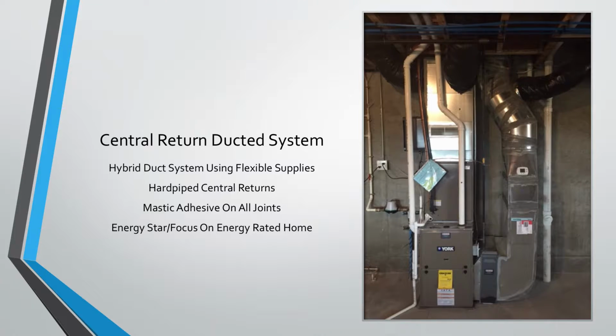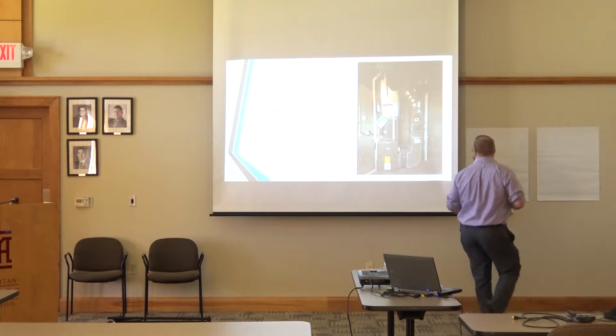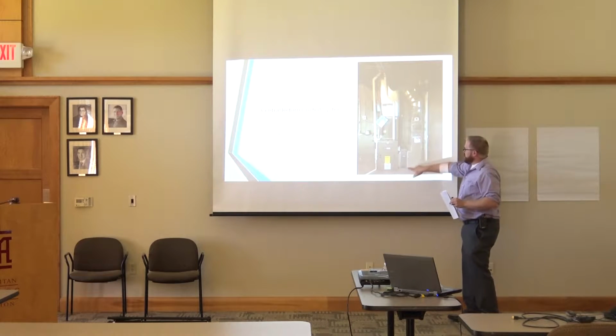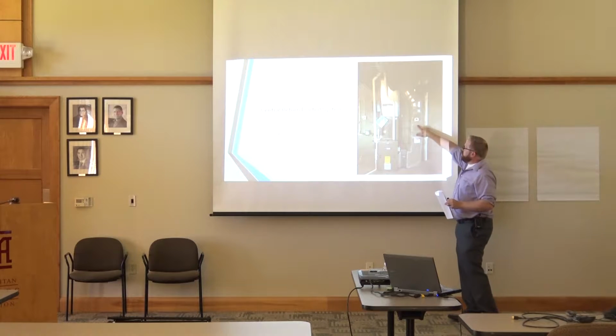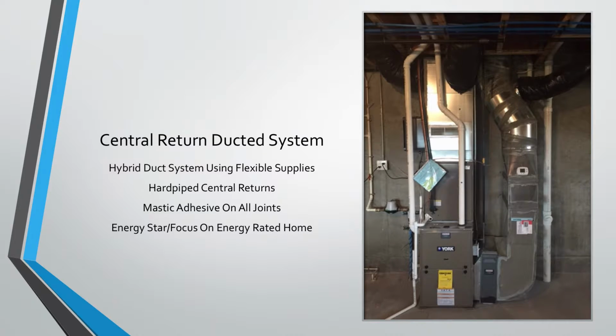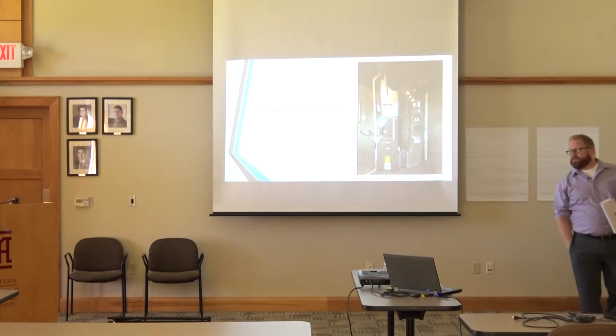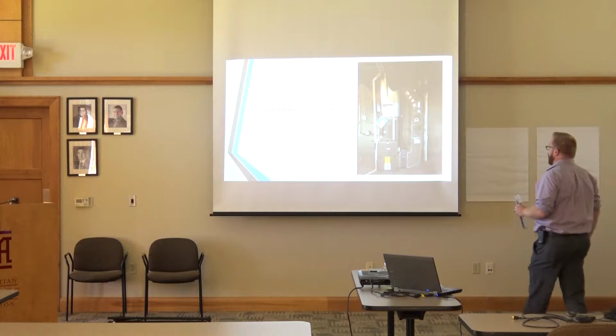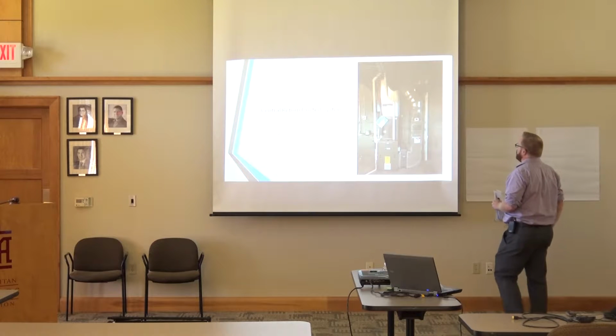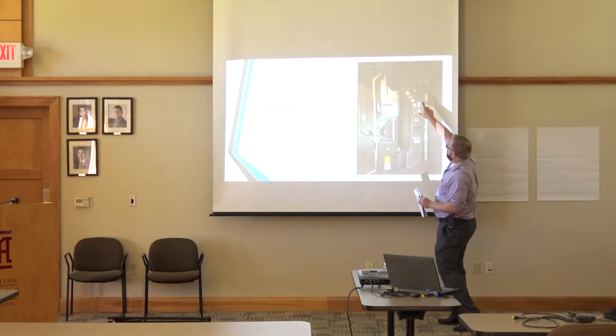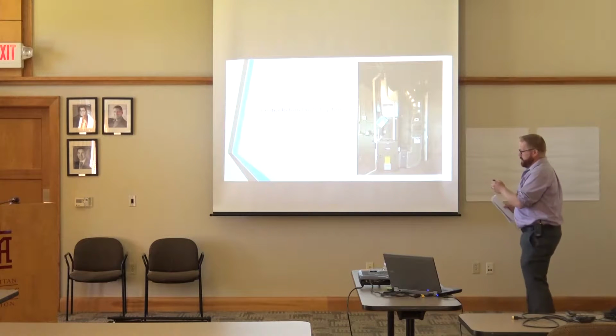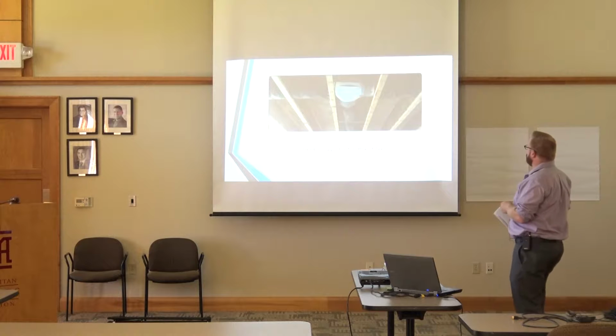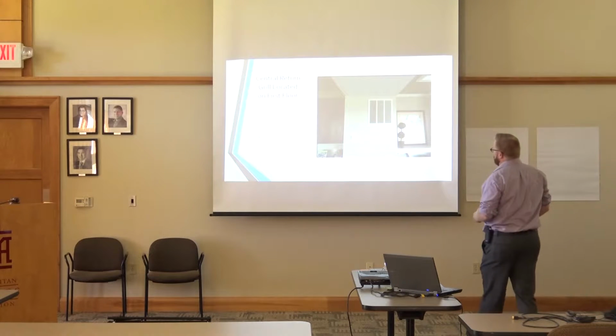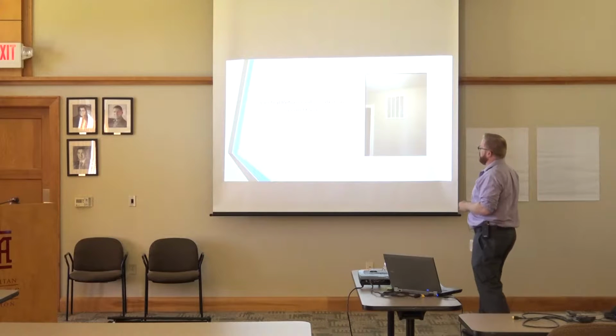So this is just a picture of an installation that we've done, and you'll see the mastic here as well. You can see on all these joints, these are all mastic joints. It's all painted on with a brush. So again, it's very labor intensive, but the sealing properties are very good. And this is showing the duct chase that goes up to those return grills that was shown here. There's a duct chase that goes all the way up from first floor to second floor.